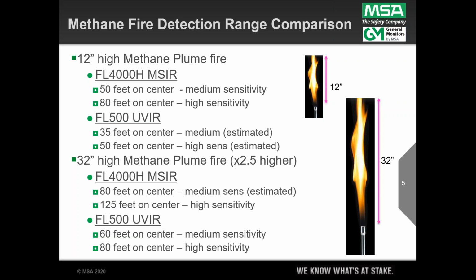So again, as I've mentioned, it's maybe not quite double here, but you can see that the FL4000 has more sensitivity to that fire size. Now, if we go to the 32-inch high methane plume fire, now we've got some greater distances because it's 2.5 times larger: 80 feet on center for your MSIR, 125 on center for your high, and FL500 60 and 80, medium and high respectively. So what's the takeaway here? Well, I'm going to talk about later on that too much sensitivity can be counterproductive in some cases, and we'll talk about why that is.